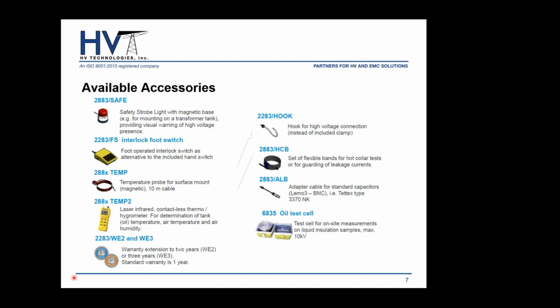Let's quickly run through some of the accessories, some of which I've already mentioned. We have the safety strobe light. It comes with a magnetic base, so you can affix it to a transformer tank, for example, and that'll provide an extra means of precaution for anybody who could possibly come into the test area. The hand switch can be substituted by a foot switch. So you have 2 options, hand or foot. It comes standard with the hand button. You have different temperature probes and contactless infrared meters, so you can go ahead and determine the tank temperature, air temperature, and humidity.